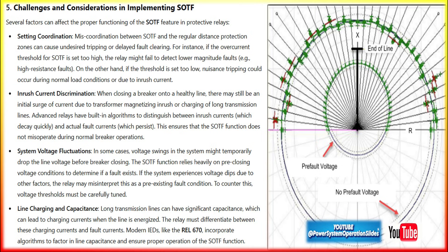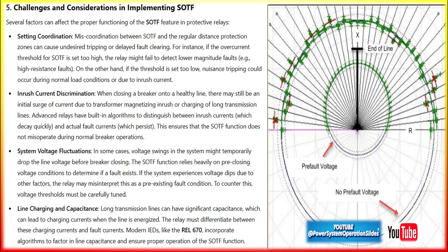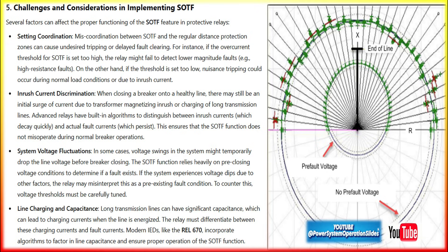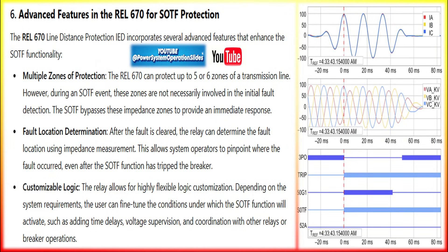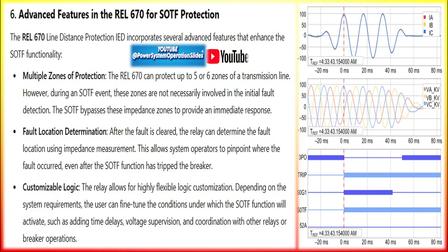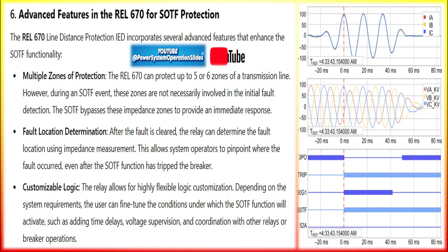To delve deeper into the SOTF function and its relevance to distance protection, let's examine more intricate technical aspects, focusing on operational challenges, relay configuration, and coordination with other protection schemes. When a fault exists on a transmission line but the breaker is open, the relay's normal distance protection using impedance measurement may not detect this fault until current flows through the line. Before closing the breaker — pre-fault condition — when the breaker is open, there's typically little to no voltage across the open breaker terminals, as the fault effectively shorts the line. This low voltage condition is detected by the relay.